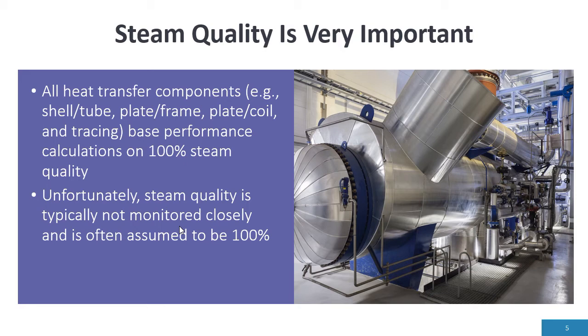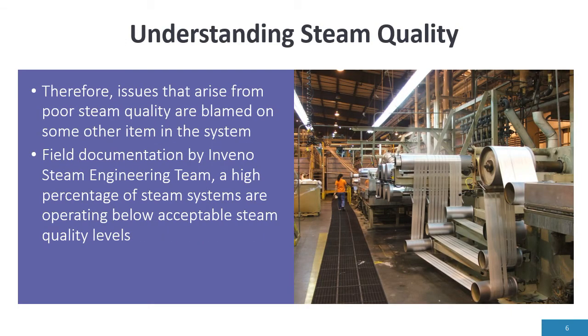In part two, we'll talk about what degrades steam quality. The key point is: don't assume steam quality is 100%. It's going to be less than 100%, and we need to know how far below 100% it is, because it will have a detrimental, negative impact on heat transfer. Poor steam quality is often blamed on various items in the steam system, and people say you have poor steam quality or wet steam — that's another term used frequently. What we're referring to is steam quality, but if there's no measurement of it in the facility, we have no basis to say yes, it's due to wet steam.